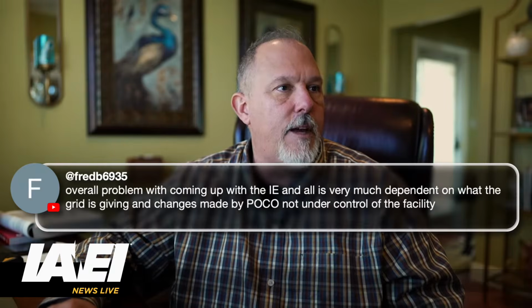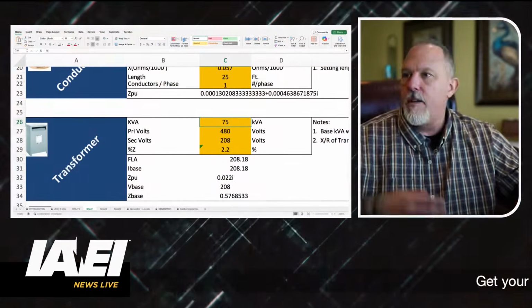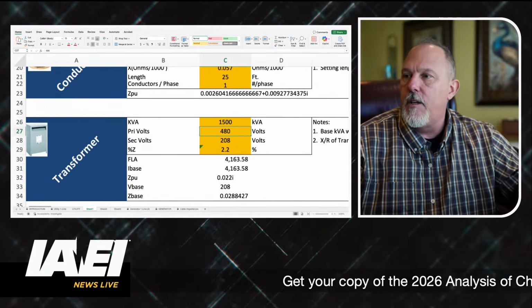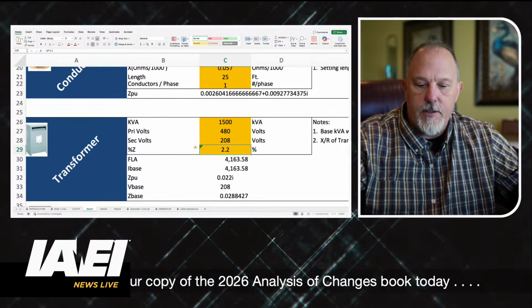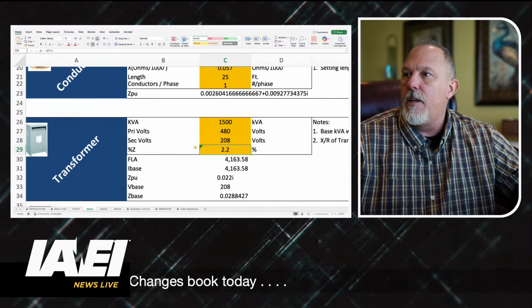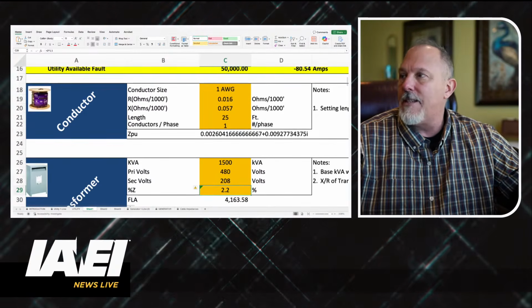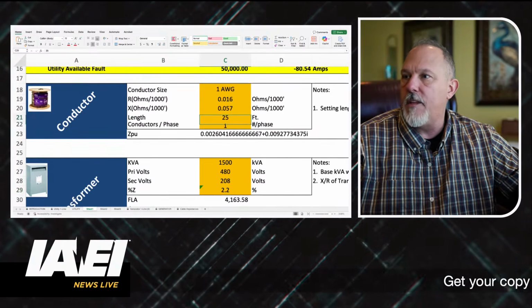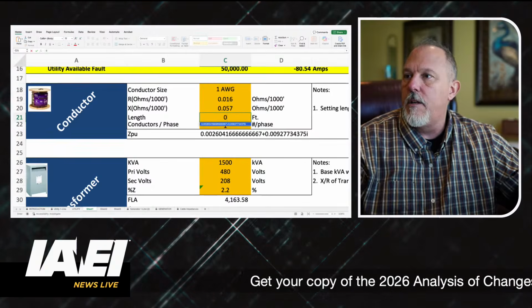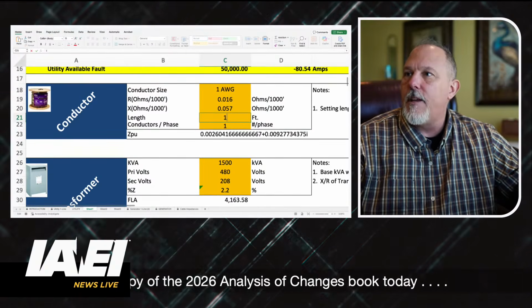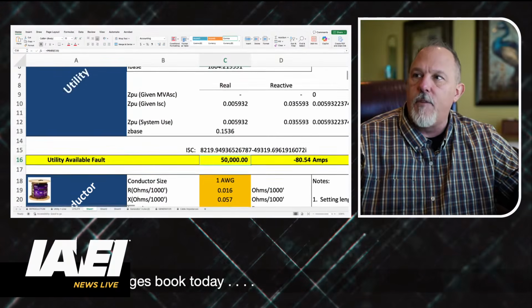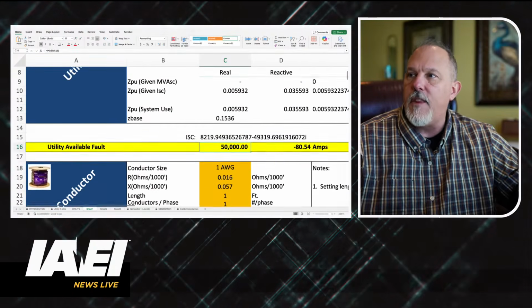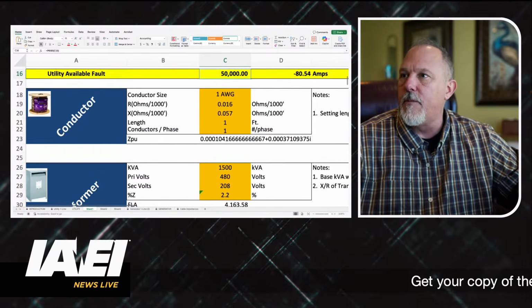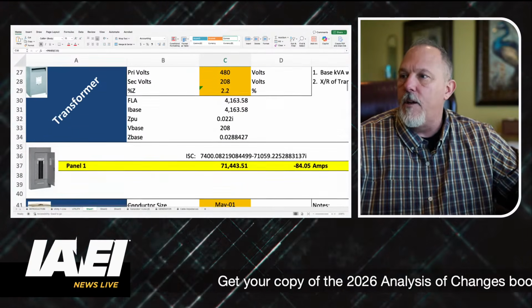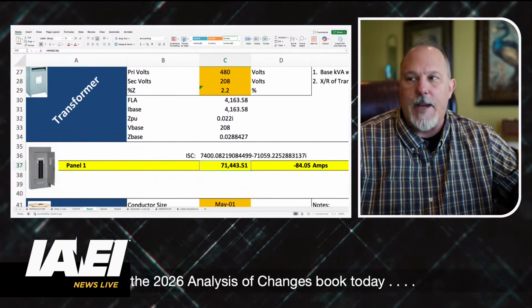All right. So say we have a 1500 kVA transformer, 480 to 208, 2.2% impedance. For the available fault current on the line side, I'm going to make the length 0 feet, I mean 1 foot. I'm starting with an available fault current of 50,000 amps. That's this C16 number. On the secondary of the transformer, I've got 71,000 amps.